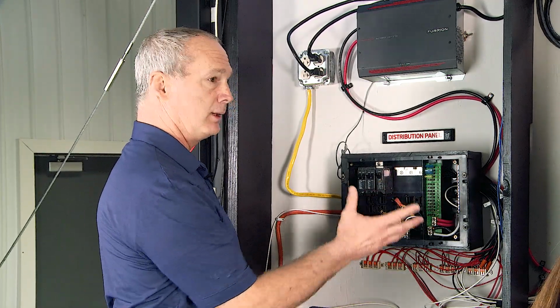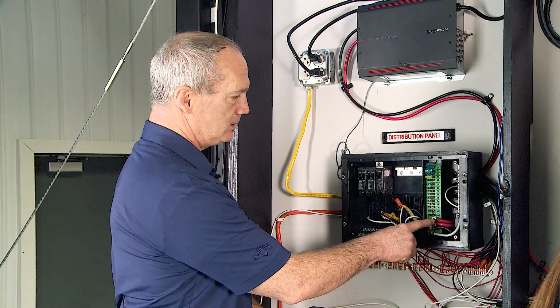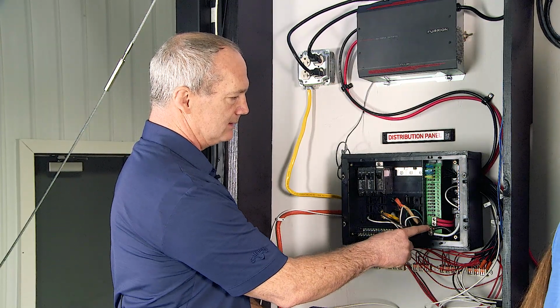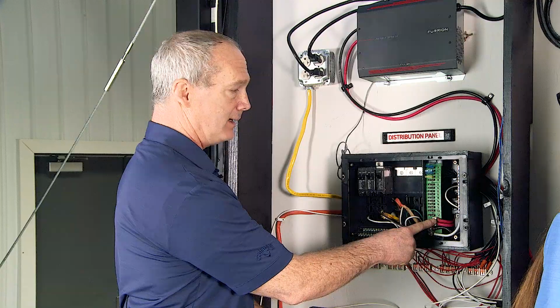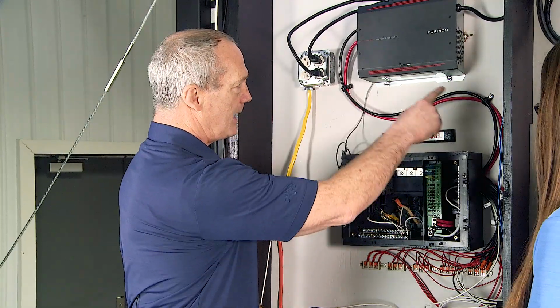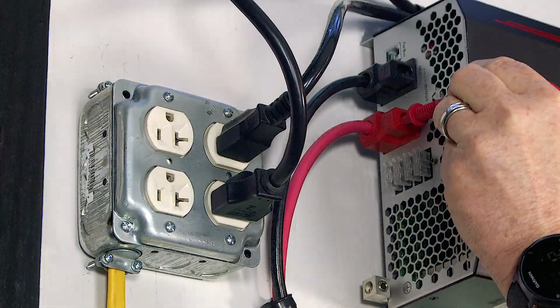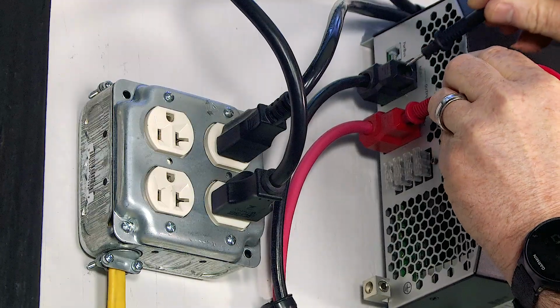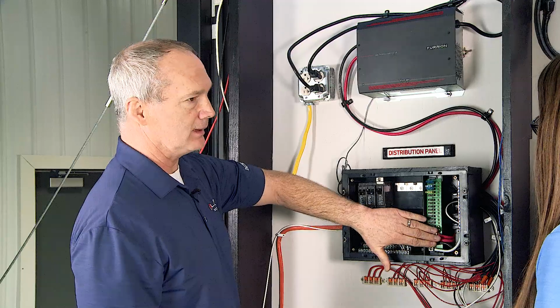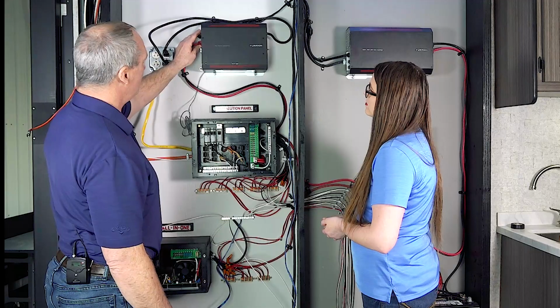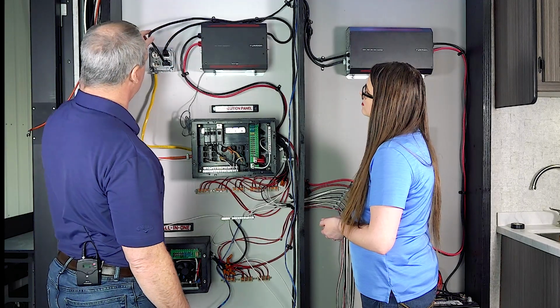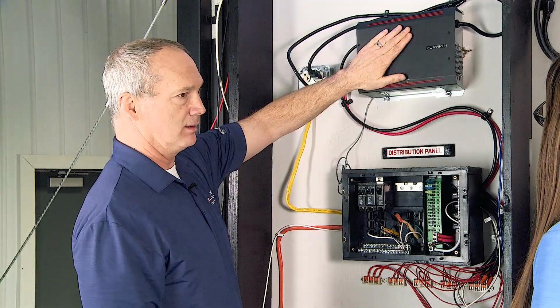It could be, but what you're going to look for here is that 12 volts, and if it's not there, then you're going to walk it back all the way to the converter, and check the wiring here at the contacts on the converter. That eliminates this wiring and this contact. Then you're going to move a little bit further into the power that runs the converter.